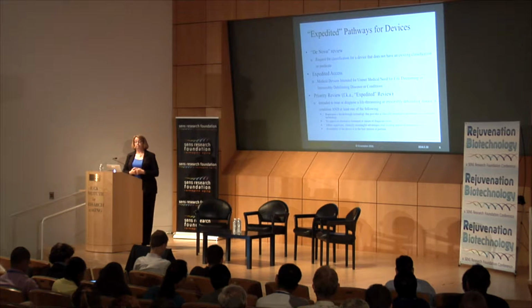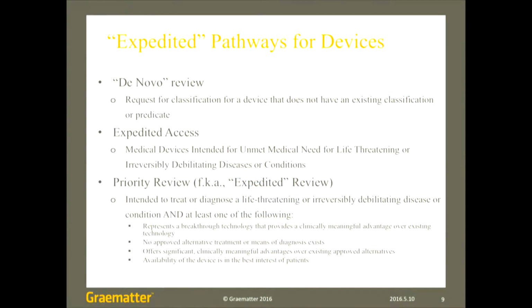But what if you have a new device that's never been seen before? The regulation says if we don't have anything like it, if you can't compare it to something that's already there, you're automatically Class 3. Well, Class 3 is supposed to be for high-risk devices. And a lot of the new technology devices are not high risk, they're just new. So you need to go through a process by which you get an official classification for that device. So that's what a de novo is. And it allows you to not go through a PMA process, but maybe go through a 510K process if it's a lower risk device. Expedited access, we talked about that a little bit. Priority review, this used to be called expedited. Same principle, they have made the language between the drug and the device very, very similar. There's really not a major difference.